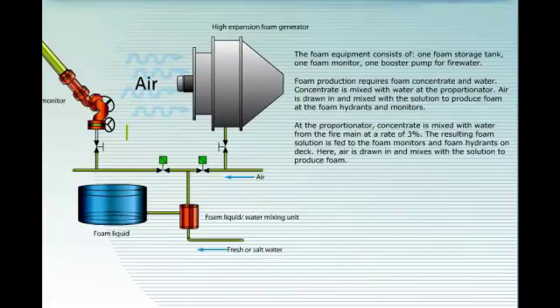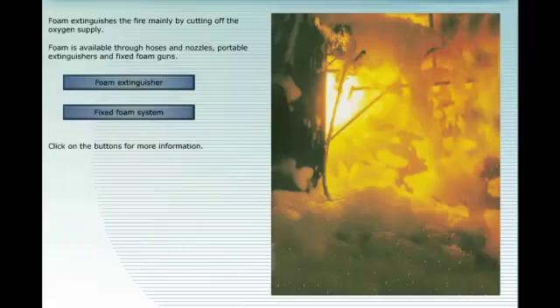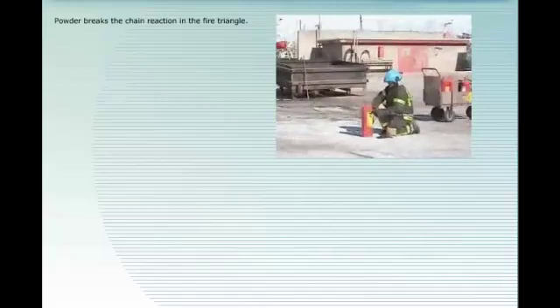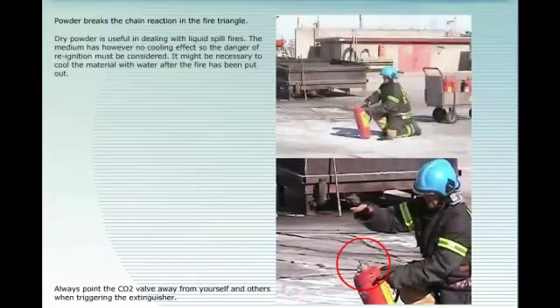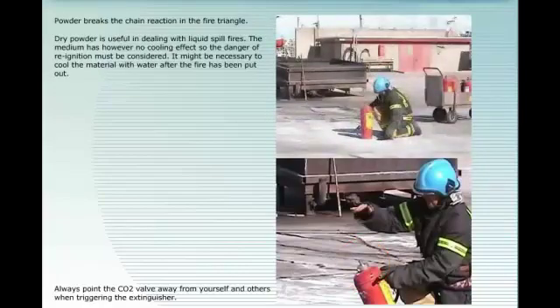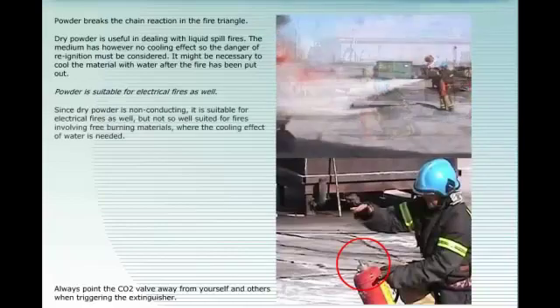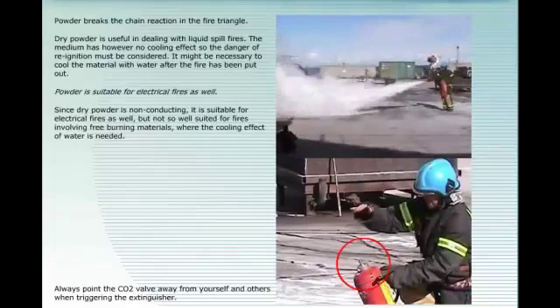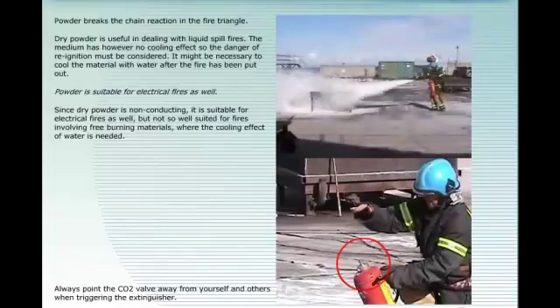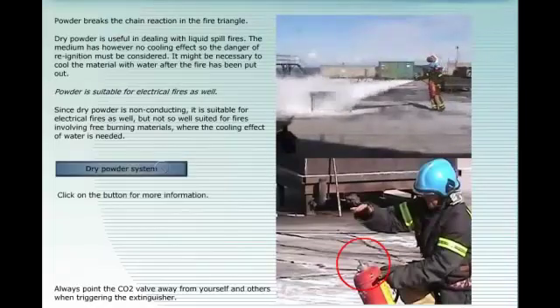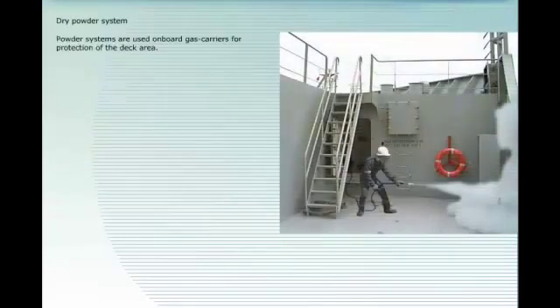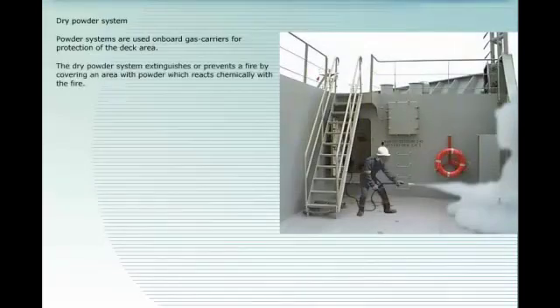Powder breaks the chain reaction in the fire triangle. Dry powder is useful in dealing with liquid spill fires. The medium has, however, no cooling effect, so the danger of re-ignition must be considered. It might be necessary to cool the material with water after the fire has been put out. Since dry powder is non-conducting, it is suitable for electrical fires as well, but not so well suited for fires involving free-burning materials where the cooling effect of water is needed. Powder systems are used onboard gas carriers for the protection of the deck area. The dry powder system extinguishes or prevents a fire by covering an area with powder, which reacts chemically with the fire. The powder is released from the storage tank through powder guns, and the system is activated from designated release areas.